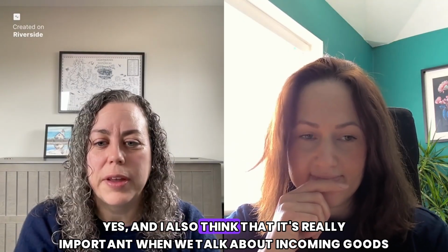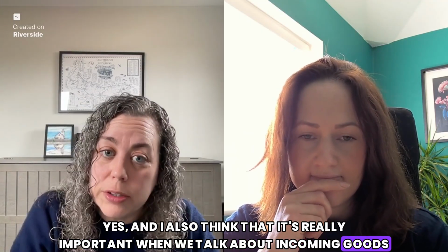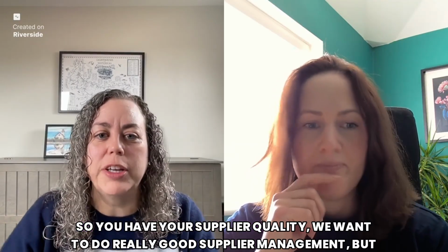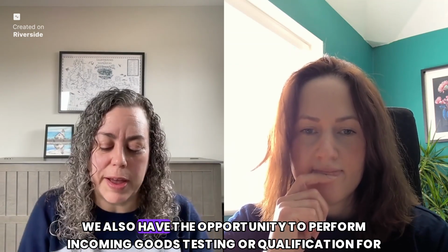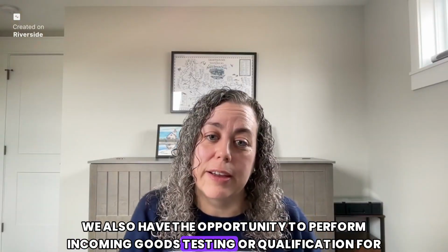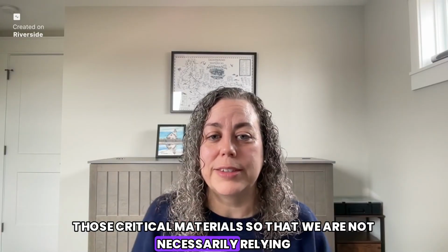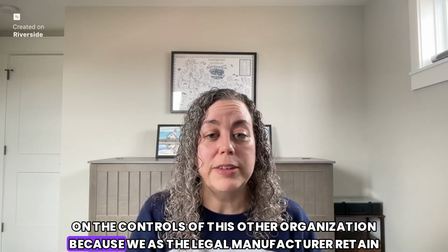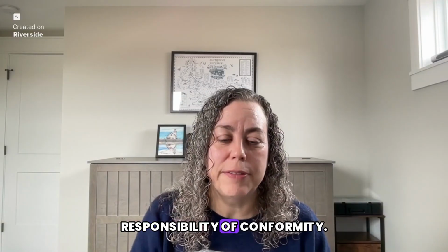Yes, and I also think it's really important when we talk about incoming goods controls, let's not forget that we have that as part of the purchasing process. So you have your supplier quality, and we want to do really good supplier management, but we also have the opportunity to perform incoming goods testing or qualification for those critical materials, so that we are not necessarily relying on the controls of this other organization, because we, as the legal manufacturer, retain responsibility for conformity.